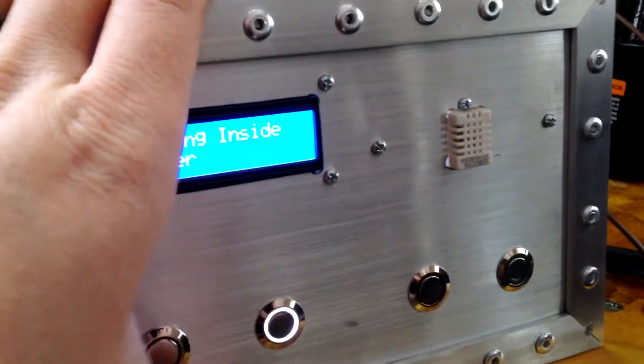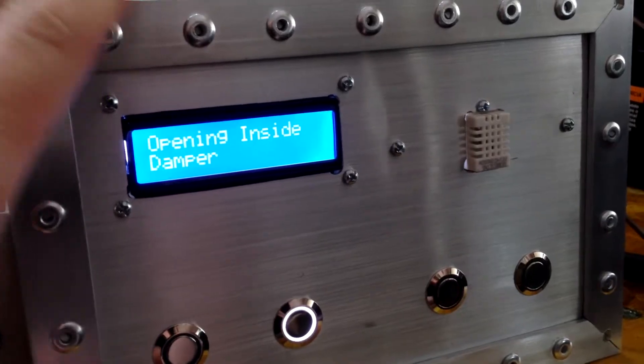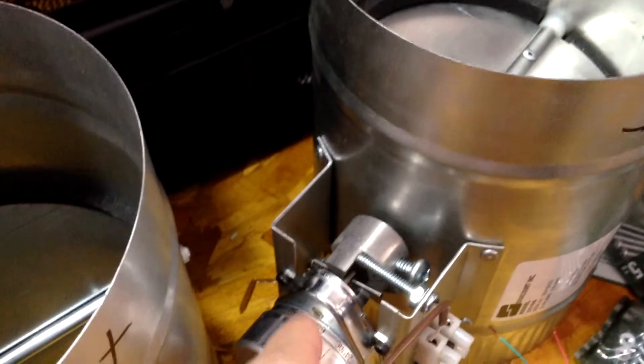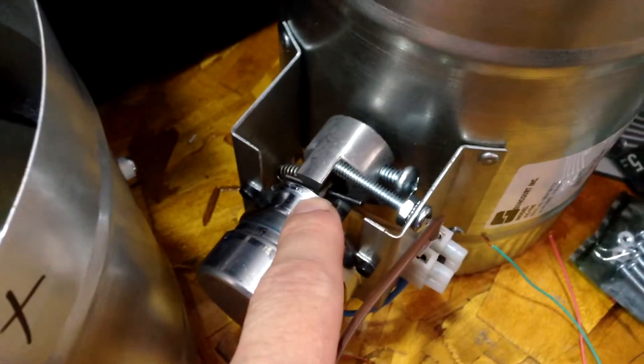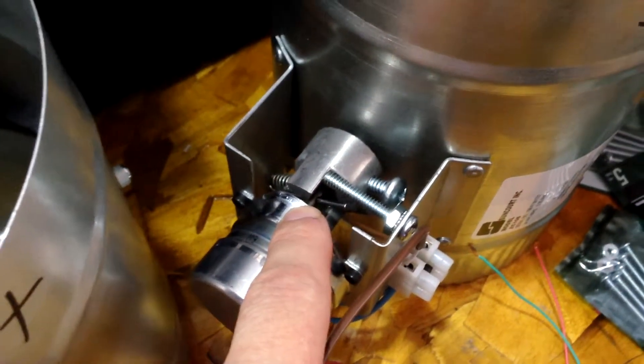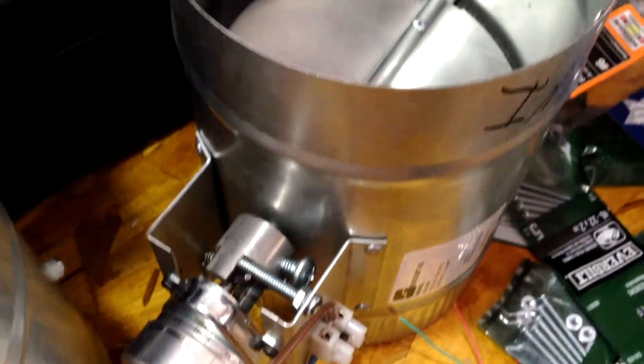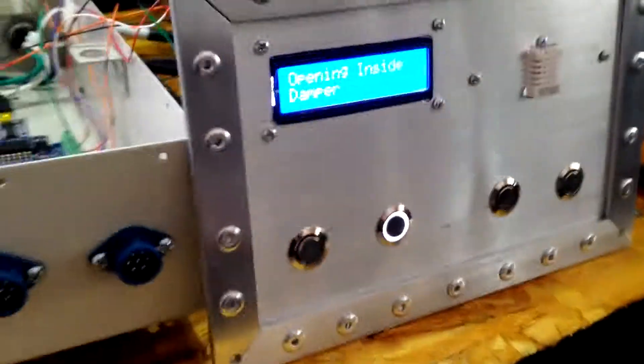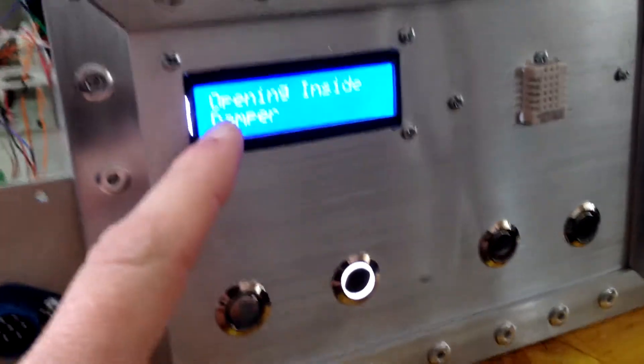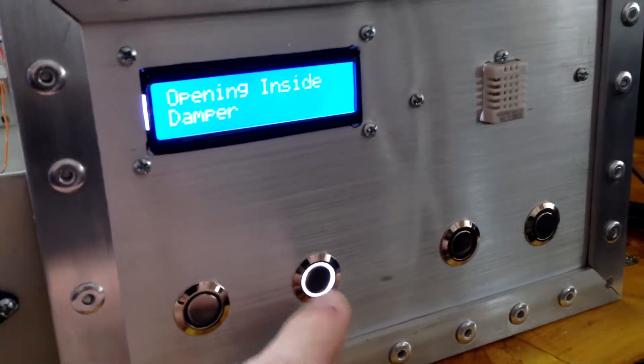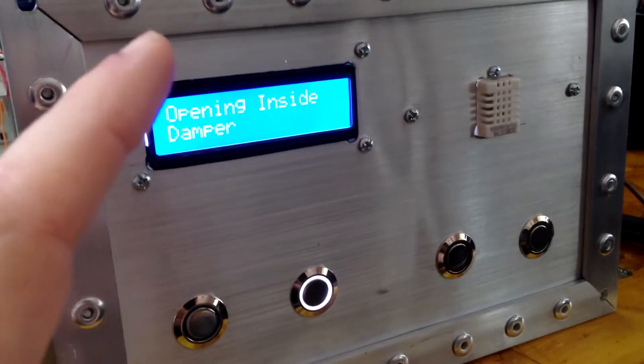Same thing if I switch it to the manual inside. It's going to, again, do that same sequence. It's going to start to open the inside damper before it closes the outside one. And then once that's complete, it'll display again. It will update to tell you that it's in manual mode and it's exhausting inside.